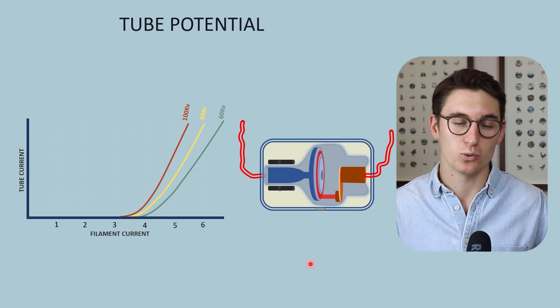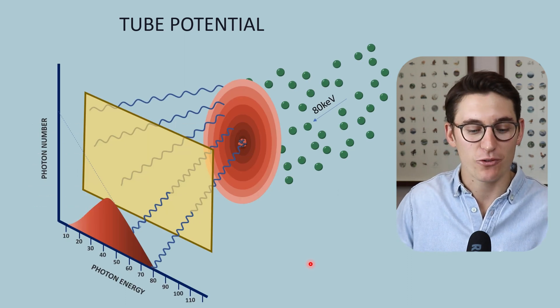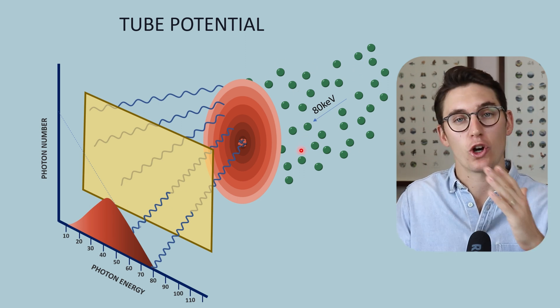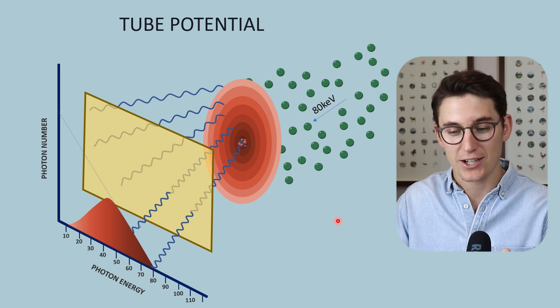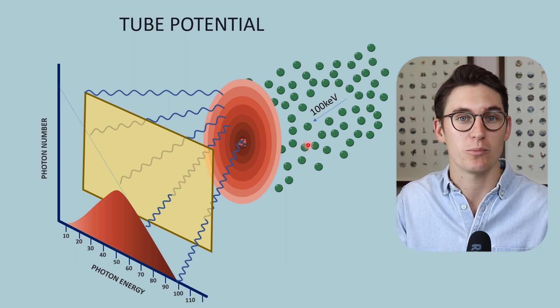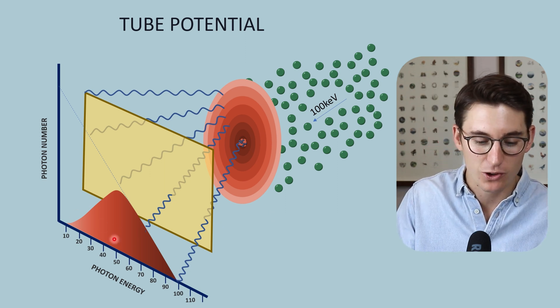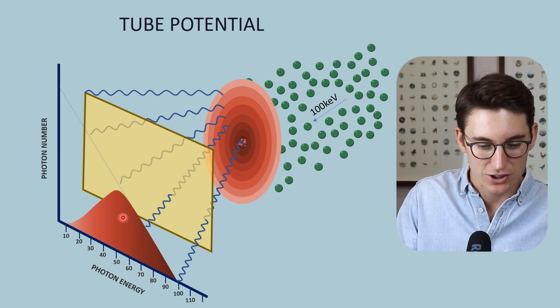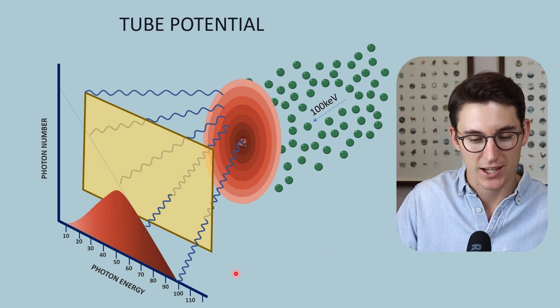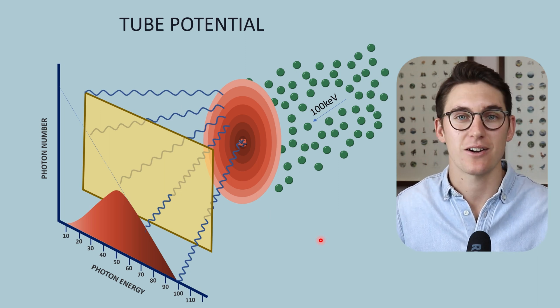So increasing our tube potential will increase the area under the curve of our x-ray beam quantity. Now what does it do to our x-ray beam quality — the average energy? If we have a tube potential of 80 keV and increase it, there will be more electrons, increasing our x-ray beam quantity, but those electrons will also have a higher energy. Our x-ray spectrum shifts to the right — we've increased the average photon energy. So not only does tube potential increase our x-ray beam quantity, it also increases our x-ray beam quality.